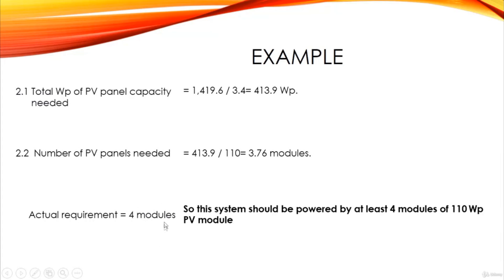Since 3.76 is not a whole number, we round up to the next integer, which is four modules. Four modules is the minimum required for our system. If we use more than four modules the system will perform better and battery life will be improved, but if we use fewer than four modules the system may not work during cloudy periods and battery life will be shortened. The system should be powered by at least four modules of a 110 watt peak PV module.